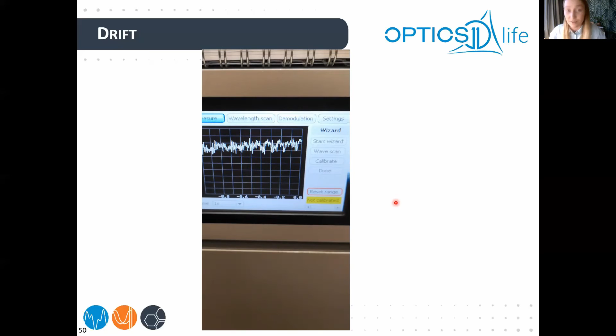You just need to wait a few minutes, maybe 3 to 5 minutes. The probe is adjusting to the medium, to the temperature. If you, for example, just took the medium from the fridge and you put the probe in, it's going to drift until the medium warms up to the room temperature. Or it can be the other way around. If you bring the sample from the incubator, then it needs time to cool down. So it's going to drift.